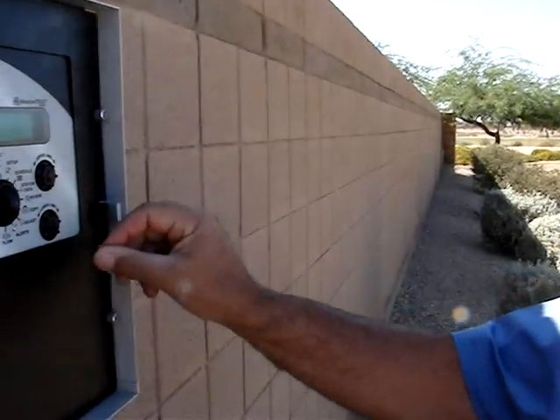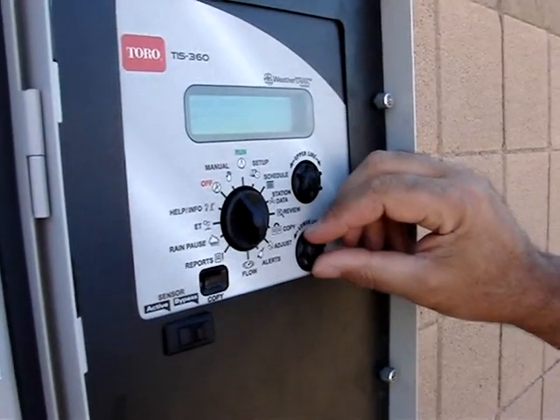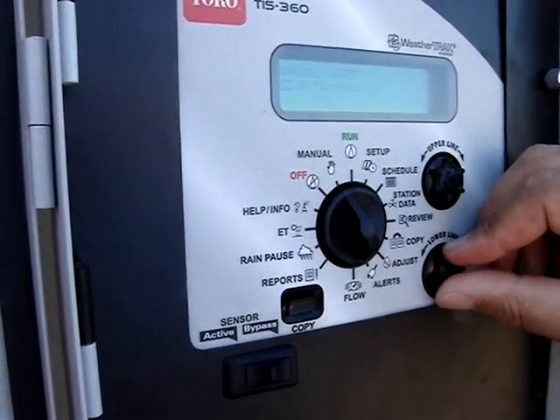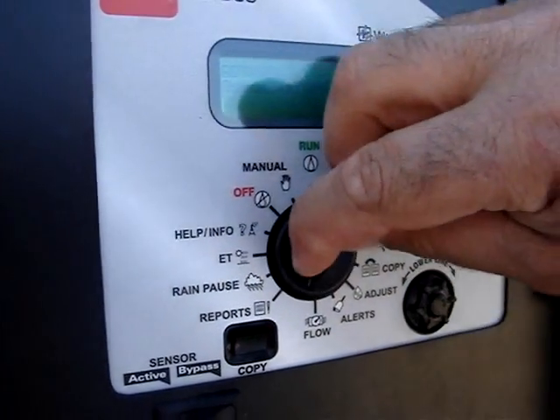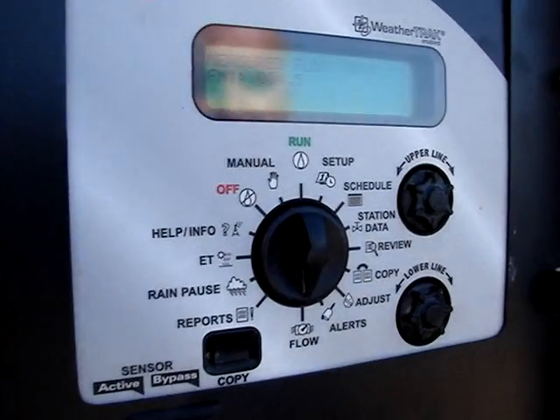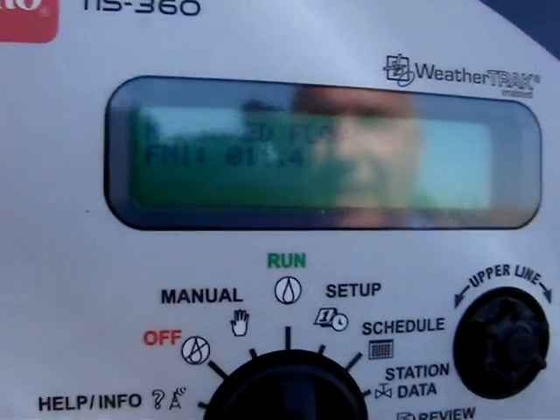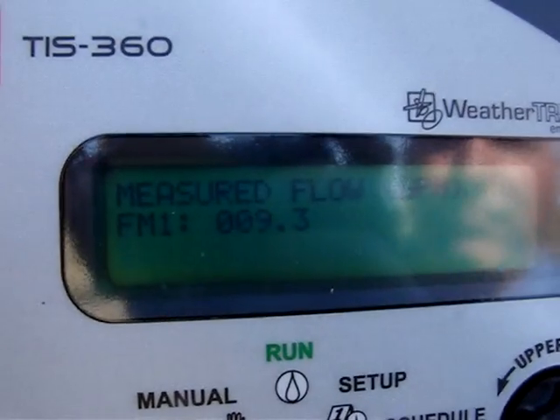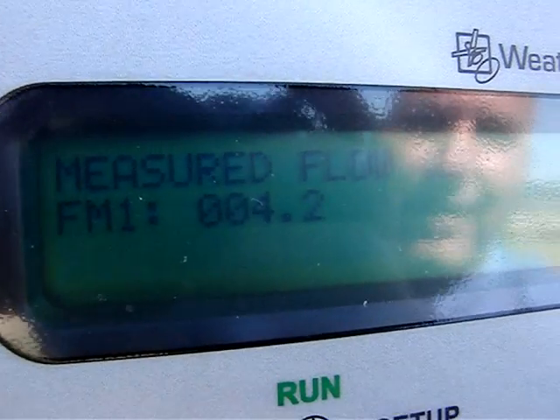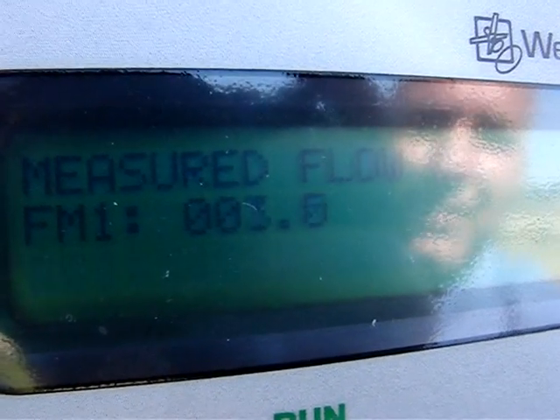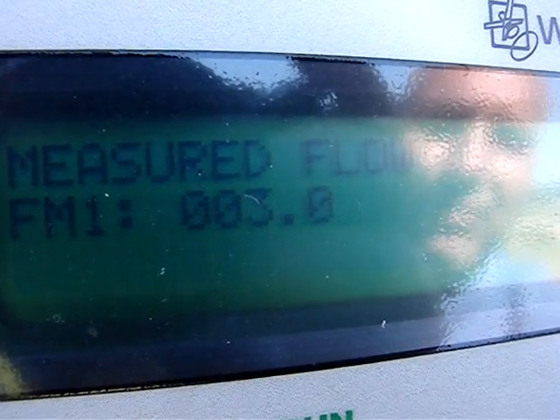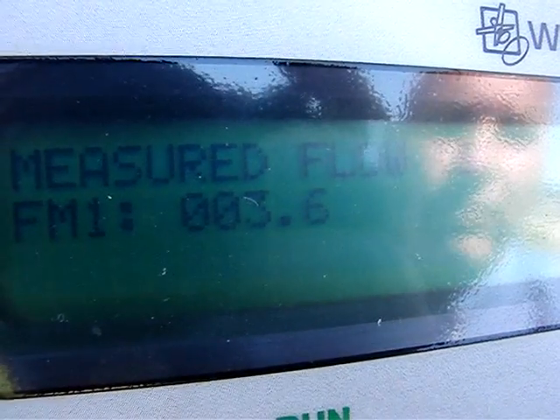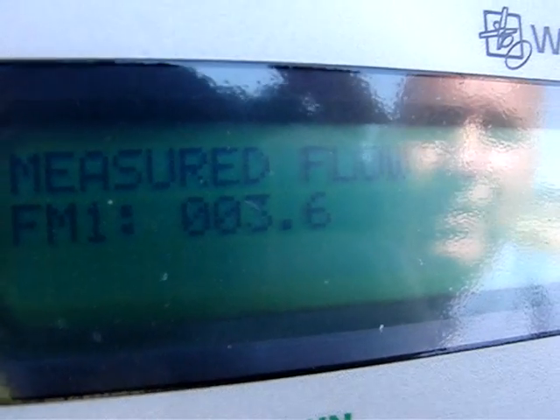Okay, now we showed you a zone that was approximately 22 gallons a minute, and this is a 2-inch flow meter, keep in mind. Now we're going to put it on a very low flow, a drip zone, where other flow sensors wouldn't have a chance at measuring this kind of water reasonably. So we're going to turn it on, and you're going to see that the drip zone is now starting up. We get a fairly high flow as the pipes fill up, so we do have to program in a delay. Then you're going to see the flow get down to very, very low flows, around 3 gallons a minute or so. And our flow sensor can measure this very accurately, very repeatably.